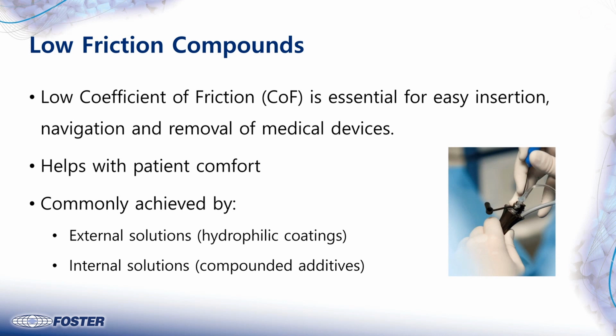So Propel is a trade name that we use for some of the low friction technology, and we're just trying to improve patient comfort. The formulations that we have, and this is a whole family of formulations, we're trying to retain as much of the mechanical properties as we possibly can. As we mentioned, once you start putting in lubricants, especially if it's a migratory lubricant, which works by coming to the surface, you might have some issues with bonding or printing on the catheter. So we need to know that ahead of time so we can use different types of lubricants.